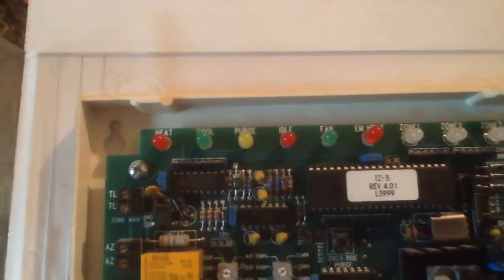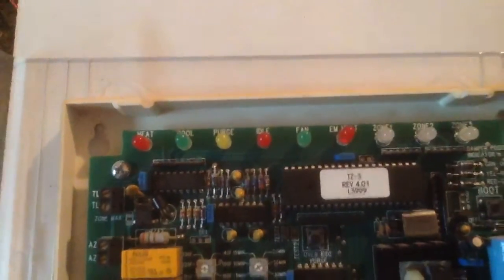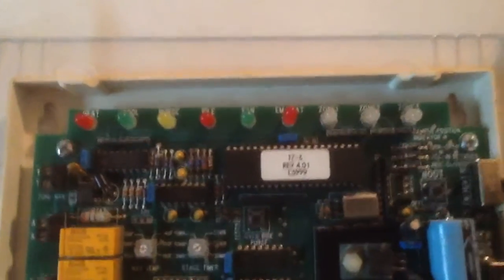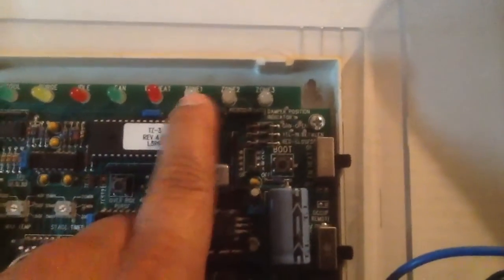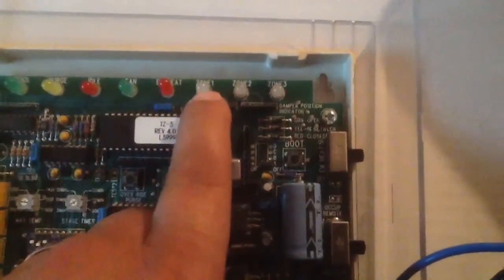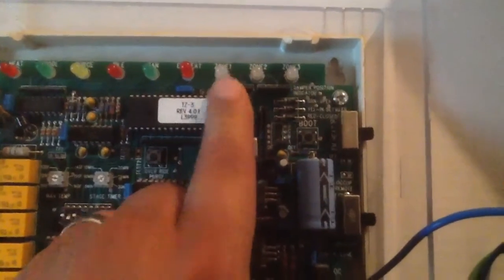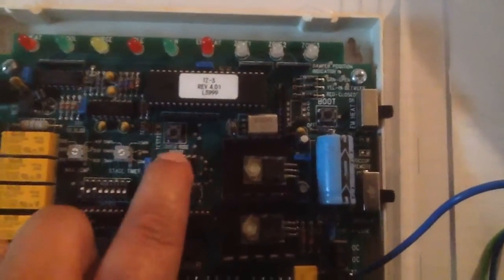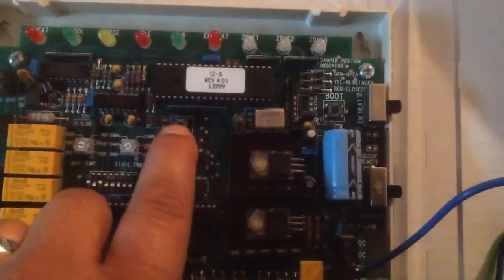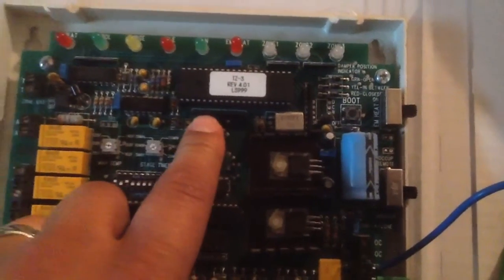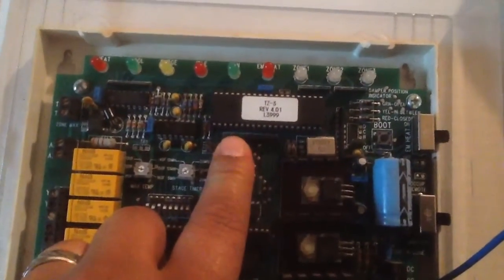Not all boards have LED lights. These here do. You've got a couple of LEDs. You'll actually see if there's a heat output. Cool. Purge means it's going to open up all your dampers and run the blower. And then your idle, fan, emergency heat. This one here will light green if there's a call in that zone, and red if there's no call, or if the zone is disabled. And then you've got an override purge button, so you can hit this for a couple of seconds and it'll override the time delays in the purge and all that stuff.